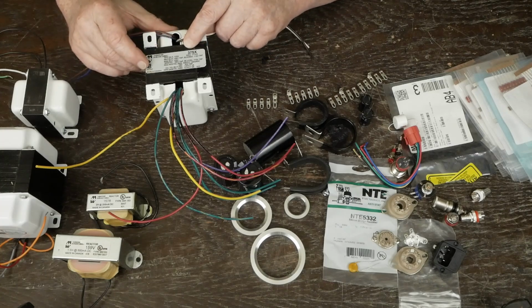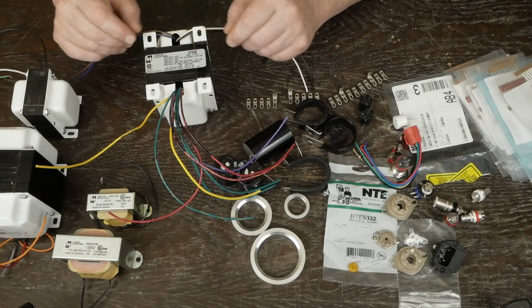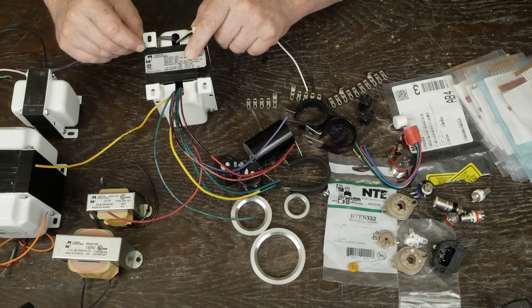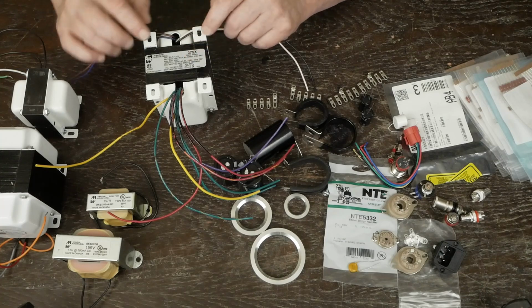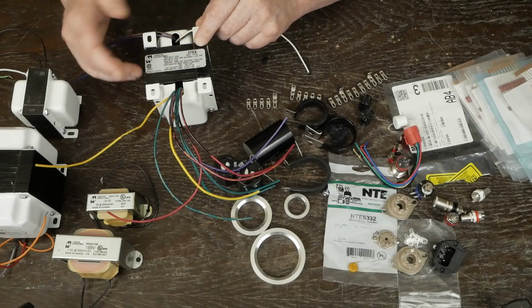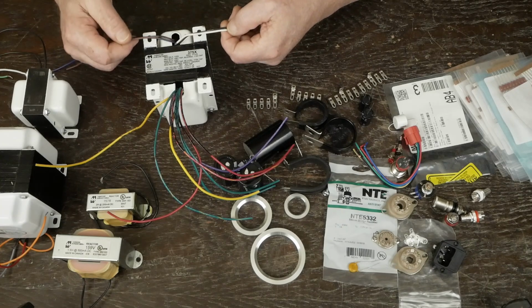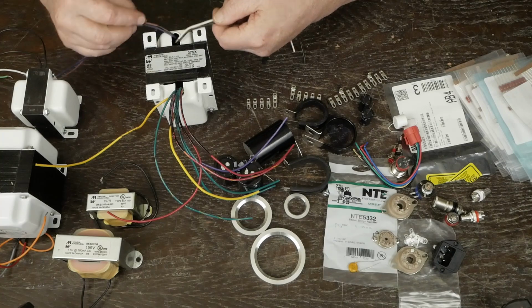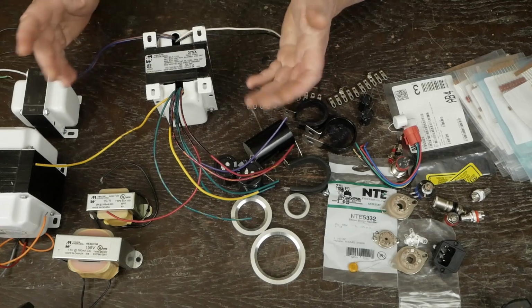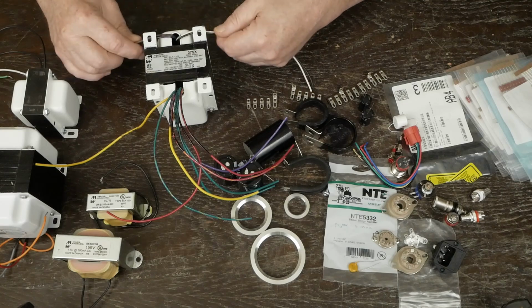On some of my projects I use the 200 series, like a 275X, the Hammond number. In this case I'm using a 375 because I needed the bias tap, this 50 volt tap for the bias supply. These 300 series normally come with a bias tap, a shield grounded to the end bell, and multi-voltage primary windings. So you can wire this up for 120 volts, 110 volts, 230, or 240—all the different voltages are capable of being wired up using the various leads that come out of this transformer.